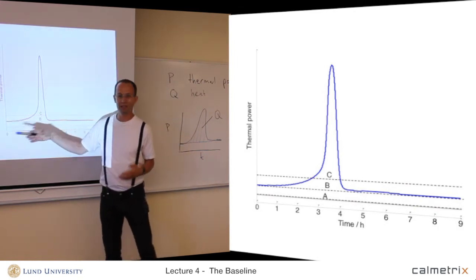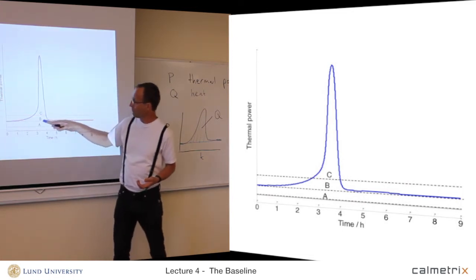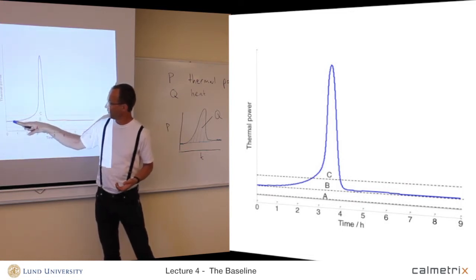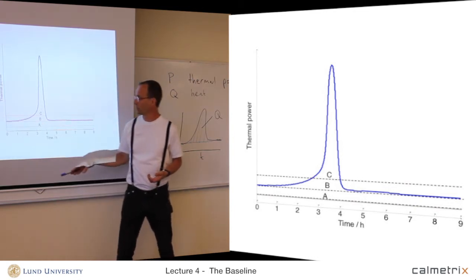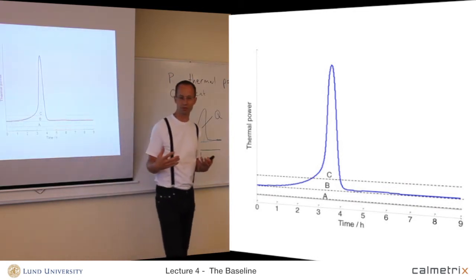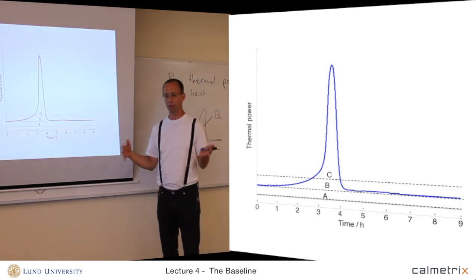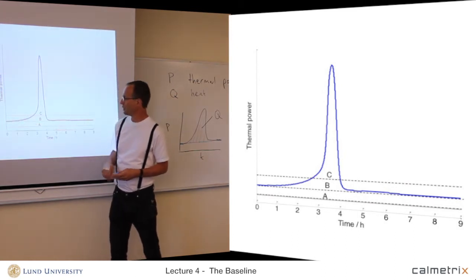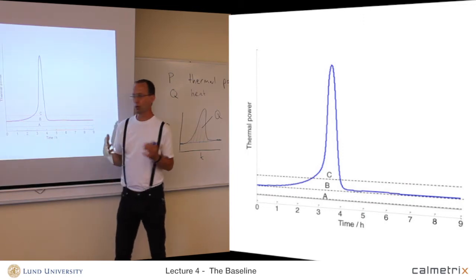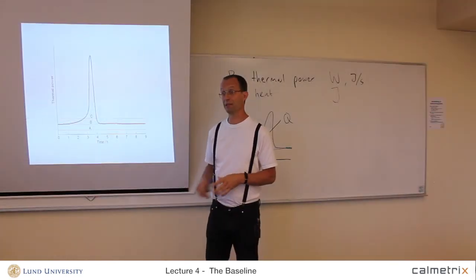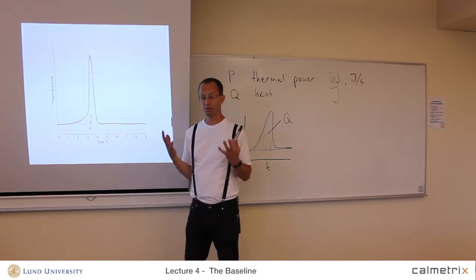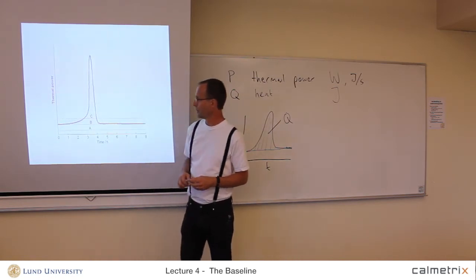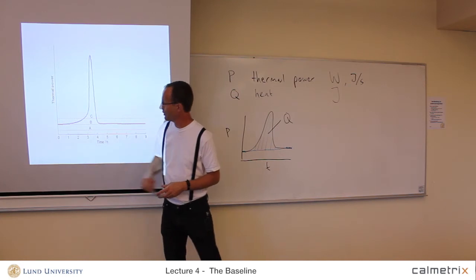As exaggerated in this example, the offset or baseline is far away from the end of the scale. But there is no reason you would get exactly zero from the instrument when no heat is produced. Because of the electrical and thermal characteristics inside the calorimeter, you get something close to zero but not exactly zero. There is always a baseline — always a shift away from zero when no thermal power is produced. So you always need to measure the baseline if you need to use it; you can't simply assume it must be zero.